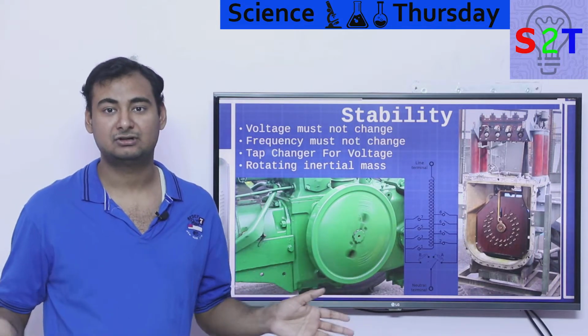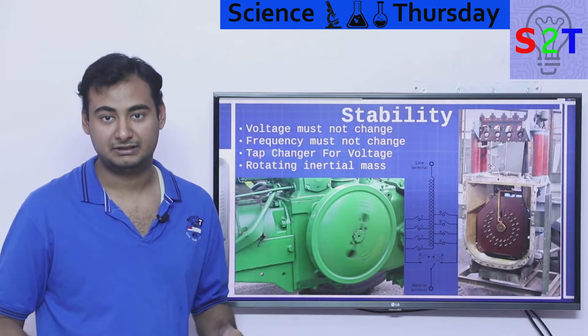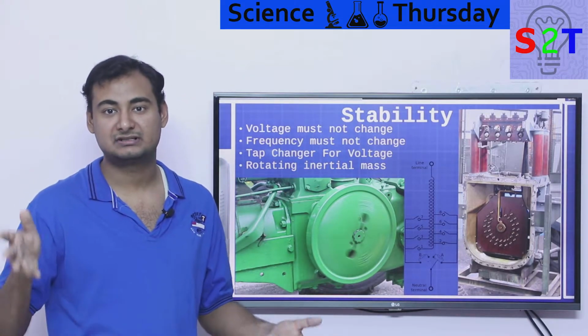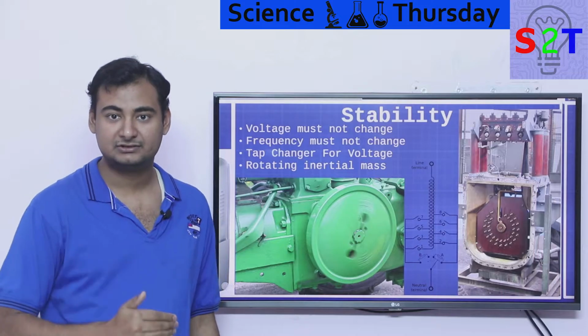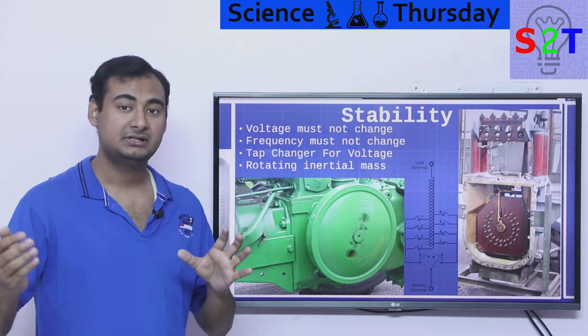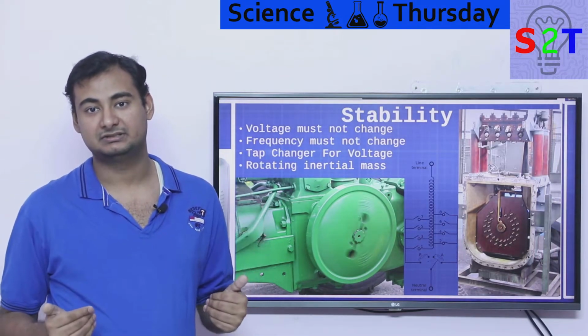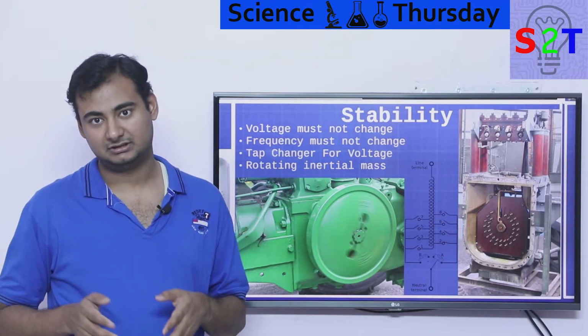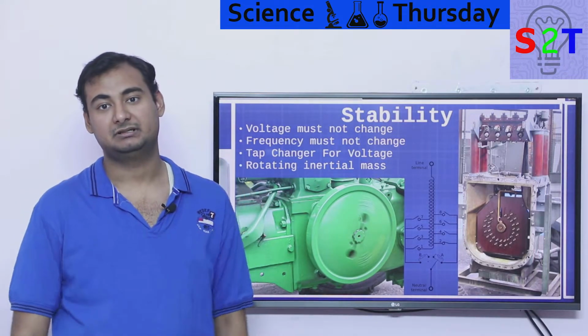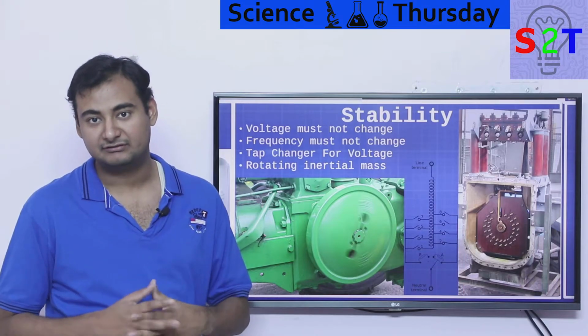A solar power plant cannot tell you, okay, 60 hertz will be maintained. If some fault occurs and the frequency going into the solar power plant changes, that's why they call them grid tie inverters. If that grid tie inverter detects, say, 58 hertz frequency, it will give out 58 hertz.